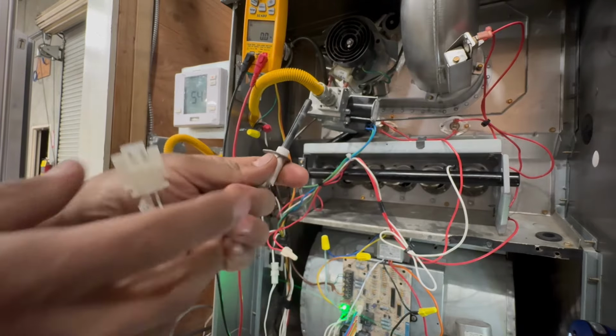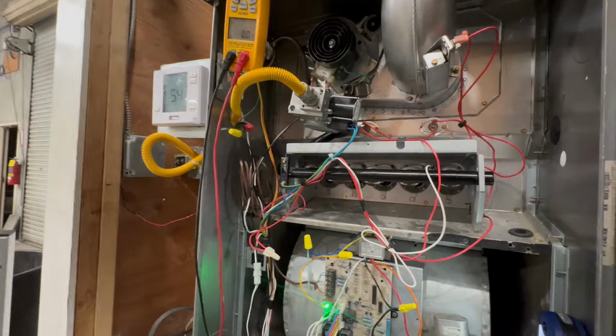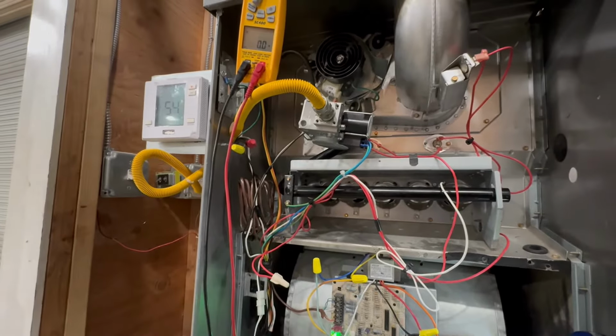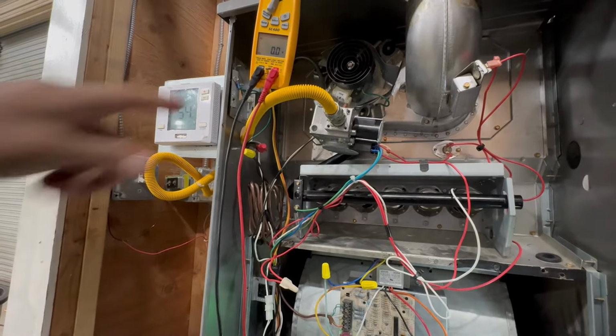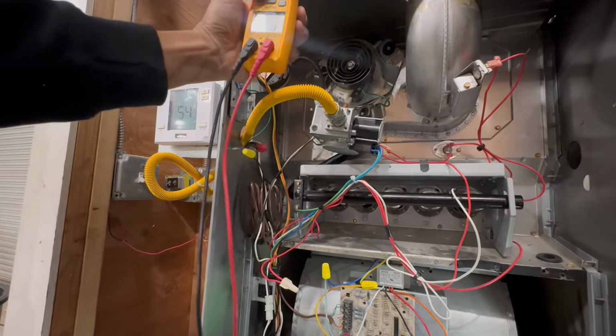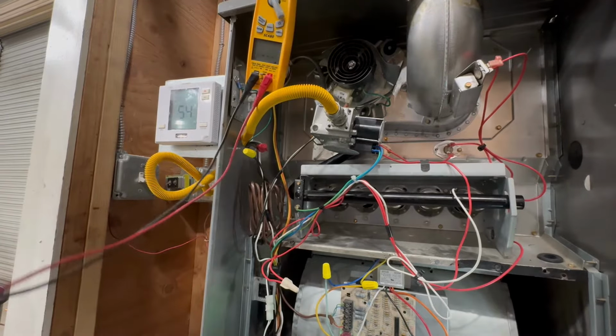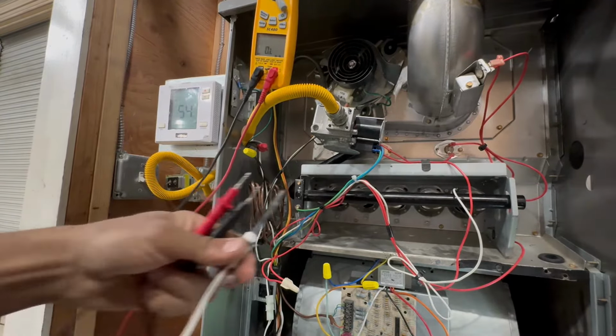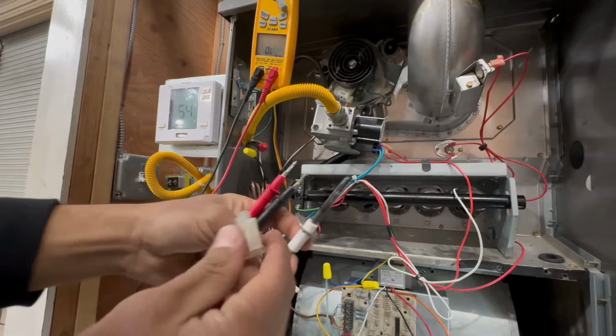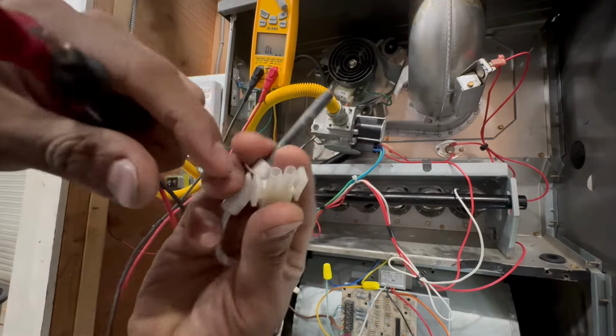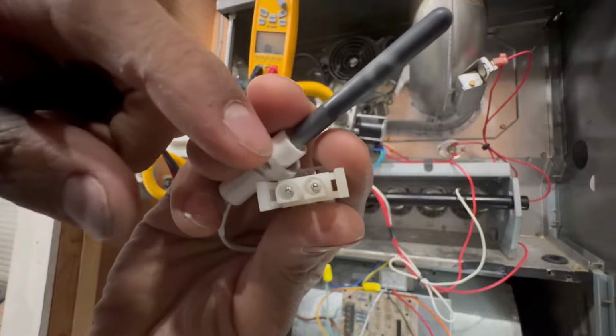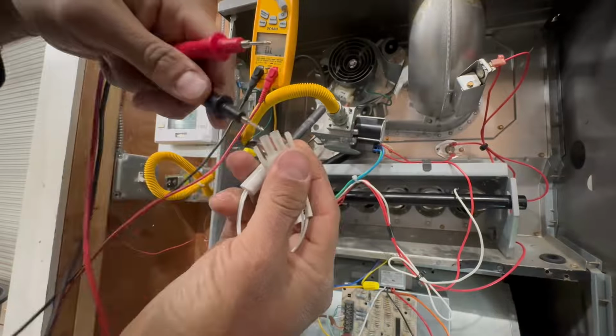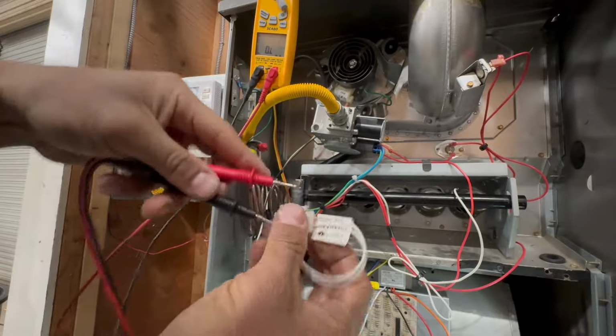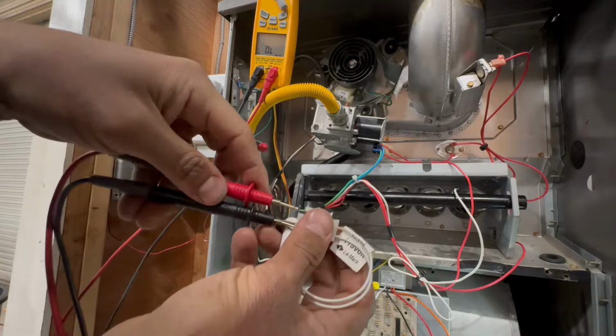But how do you check it with no power present? So I'm going to go ahead and go to my meter, right? You can see my meter there. And we're going to put it on ohms. You have to put it on ohms. And you want to make sure you get a reading. You do not want to get open line. So simply put, in here you've got the points where you connect your leads. So I'm going to just connect the leads in there, right?